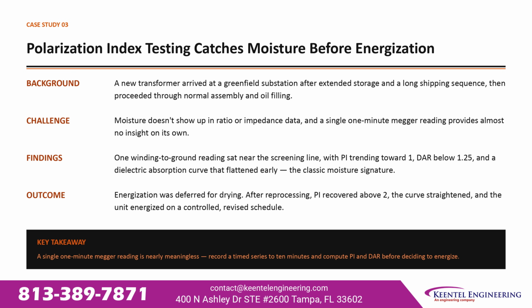One winding to ground reading sat near the screening line, with polarization index trending toward 1, dielectric absorption ratio below 1.25, and a dielectric absorption curve that flattened early. The classic moisture signature.